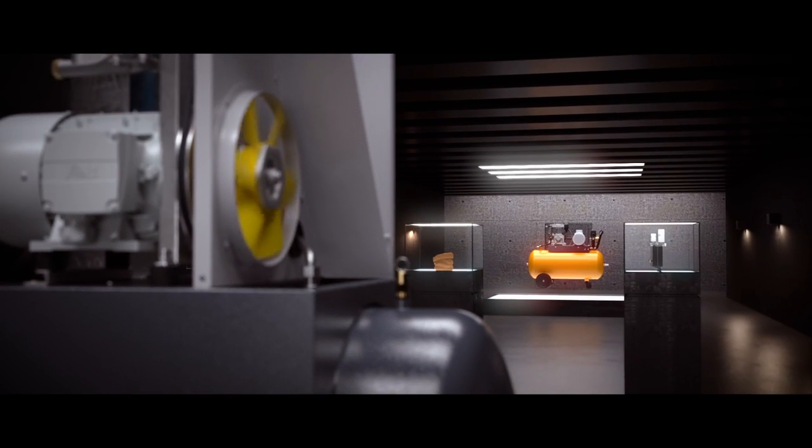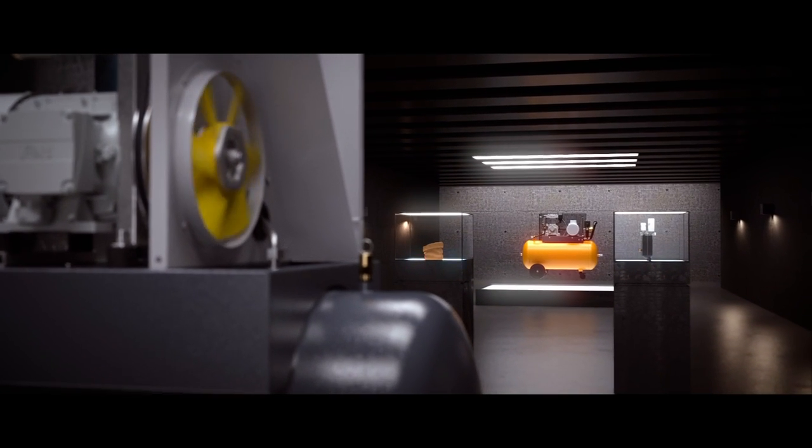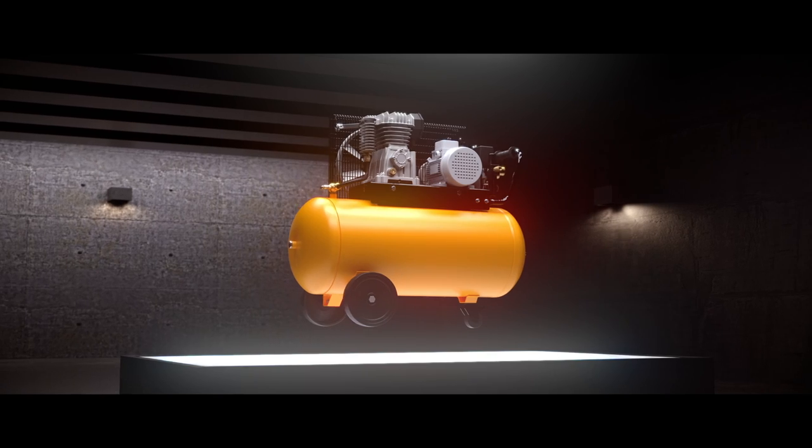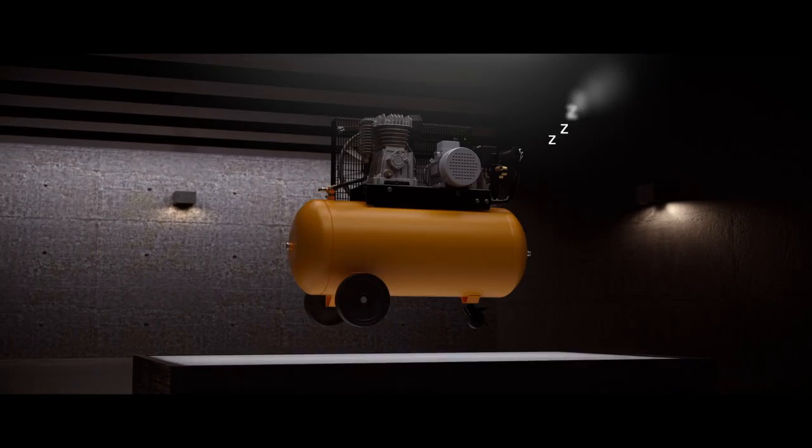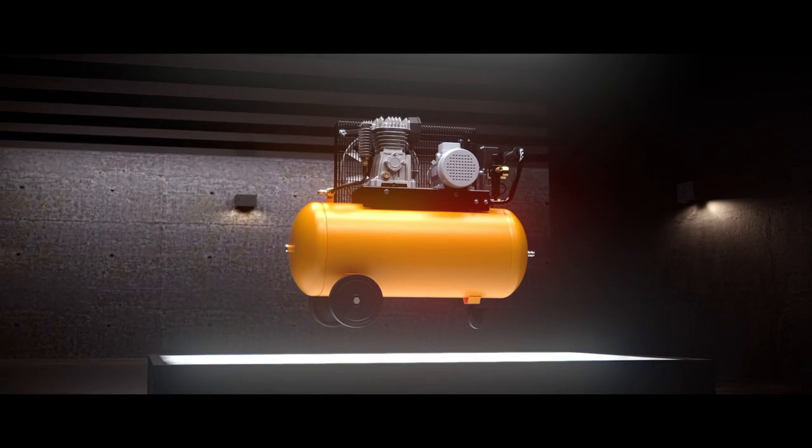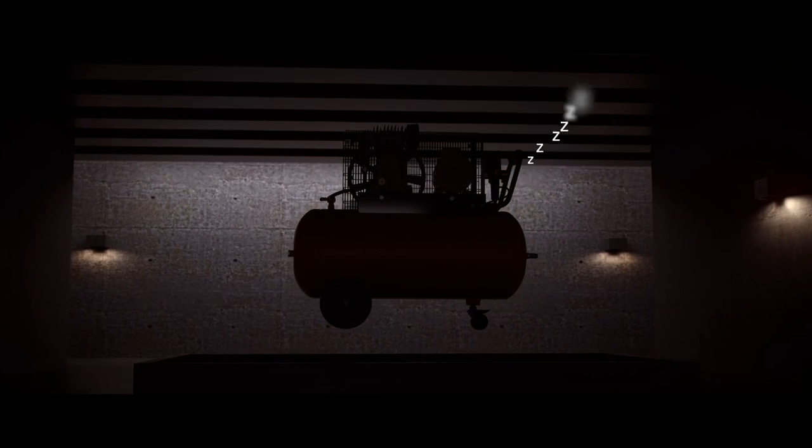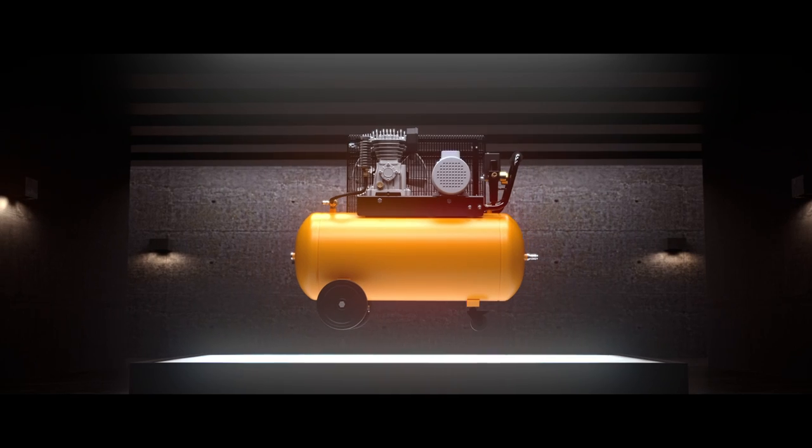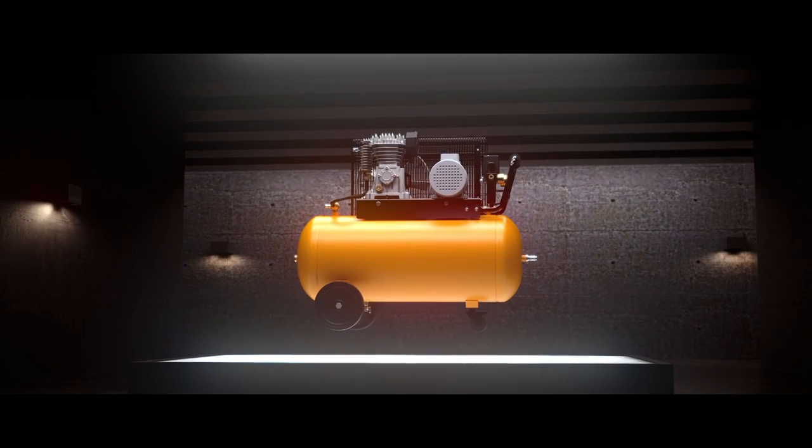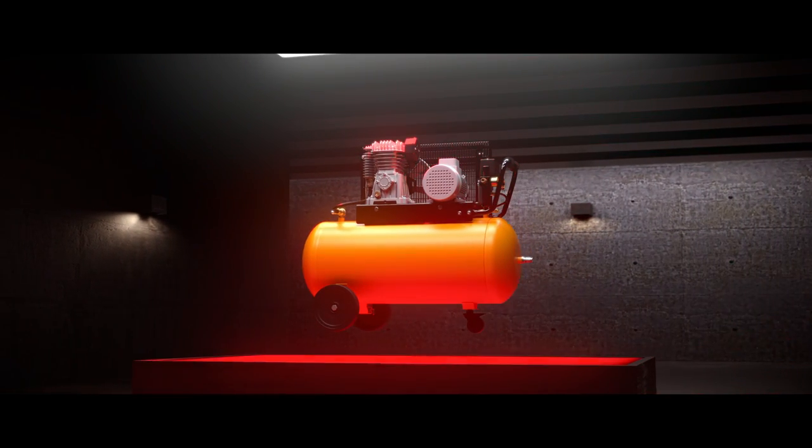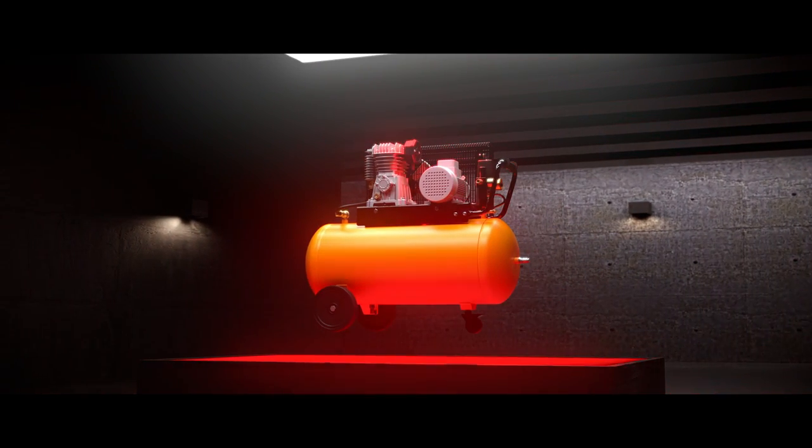Piston compressors, on the other hand, need cool-down periods. This means that they can only produce air about 70% of the time. Running pistons longer than that will increase wear and the risk of premature failures.